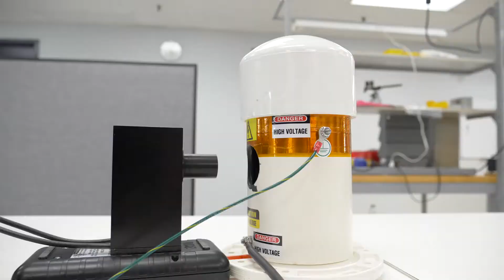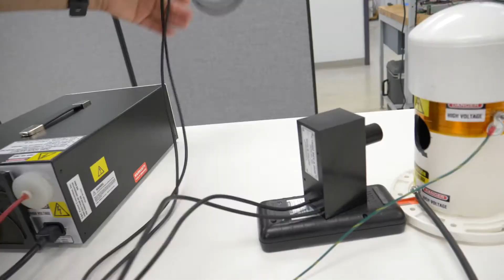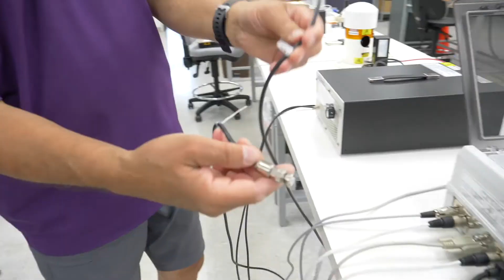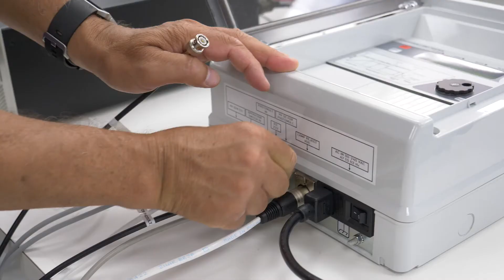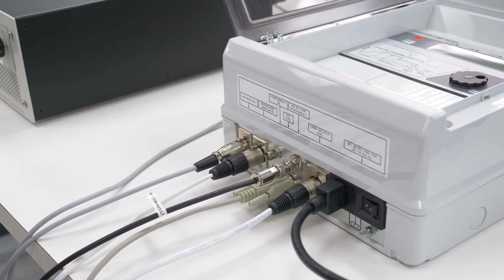The light meter must be perfectly centered with the bulb and its filament, so the light measurement will be the most effective. The last component is a connection of a light meter to the controller. This is a high voltage connection, DC high voltage for the lab light meter, and this is the returning signal from the photomultiplier that is telling us about the intensity of the light in a bulb.